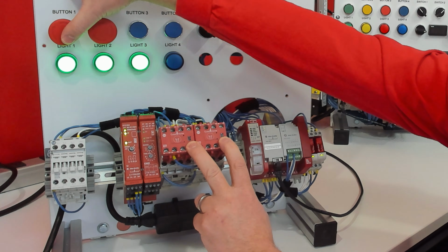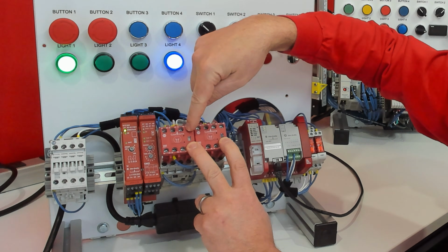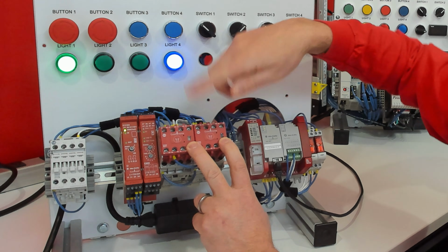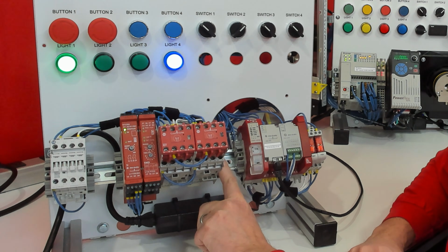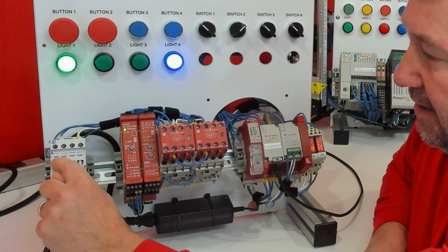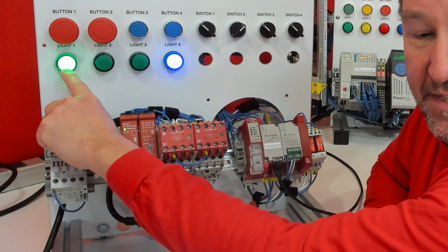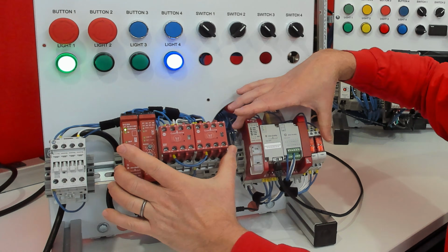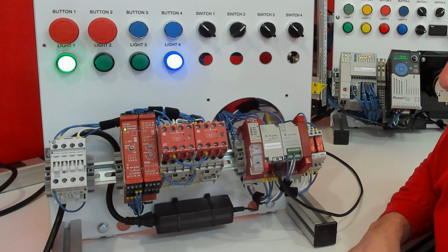So we press our e-stop, and you saw the gray pop out right there, but there is no gray popping out right here. So this contact is welded shut. This one did drop out. But notice in this case, our machine is going to continue to run. Our operator's in danger.